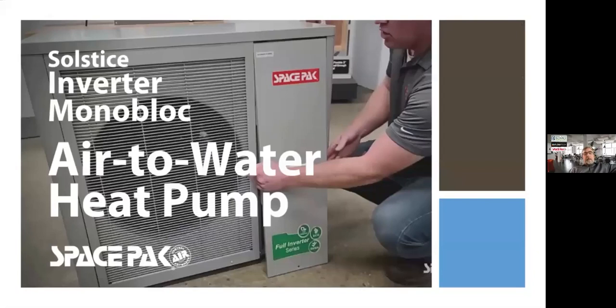The solution to this is to really switch to a hydronic system. A hydronic system means that we place a single heat pump on the outside of the building, and it contains a very, very small amount of refrigerant charge within the unit outside. The lines and connections all stemming from that particular heat pump going to the inside of the building, whatever the emitters are, are all hydronic. They're water with a little bit of glycol. One slide forward.